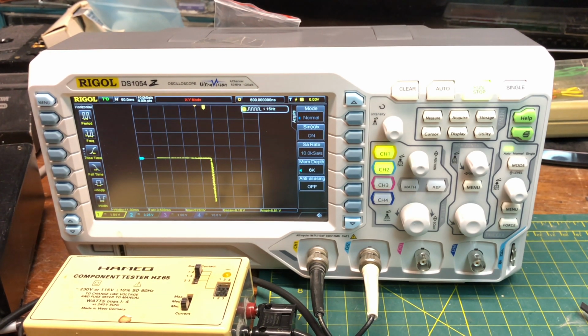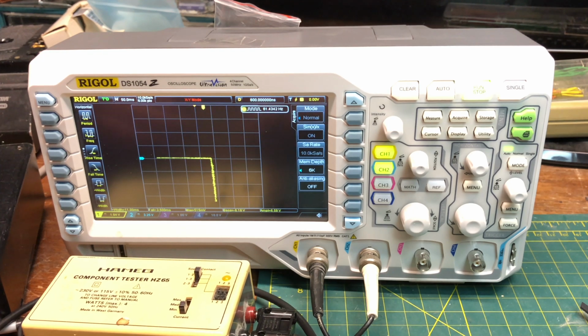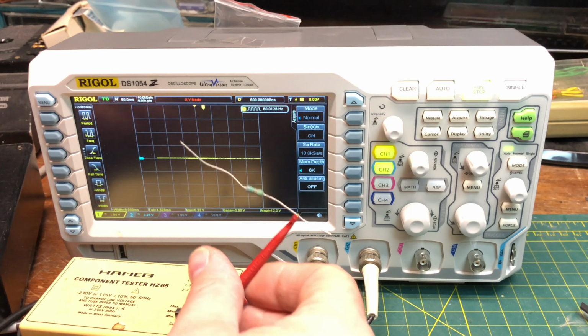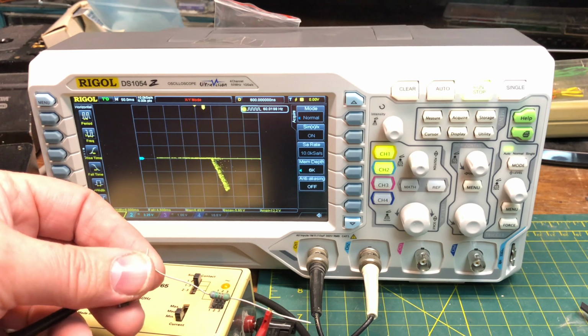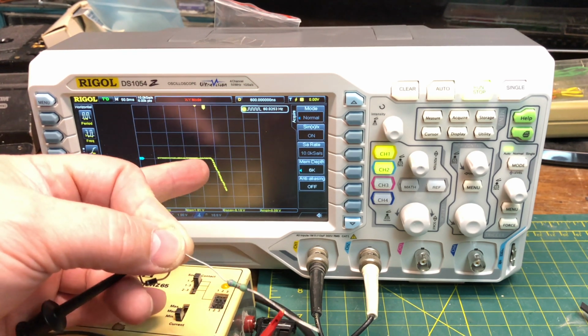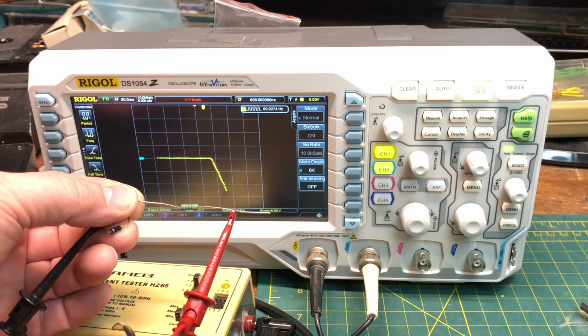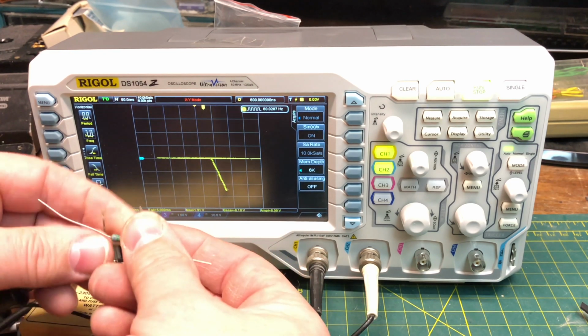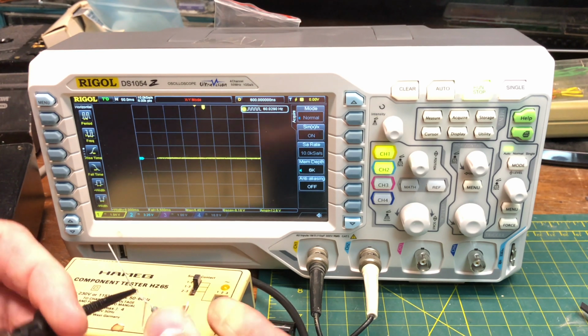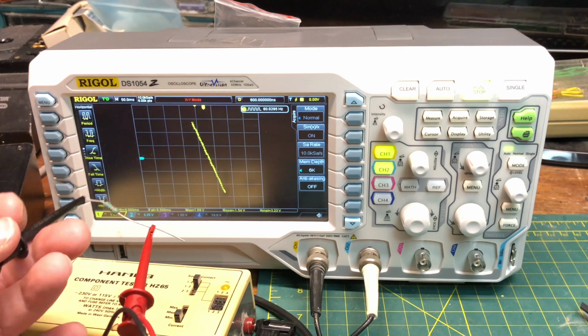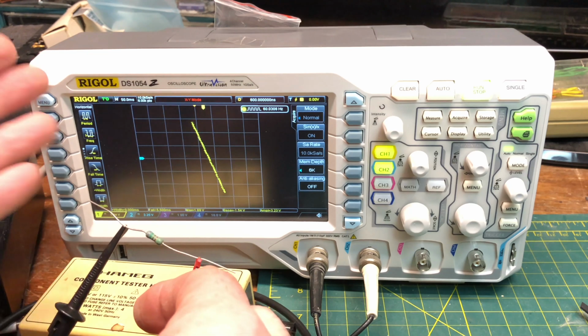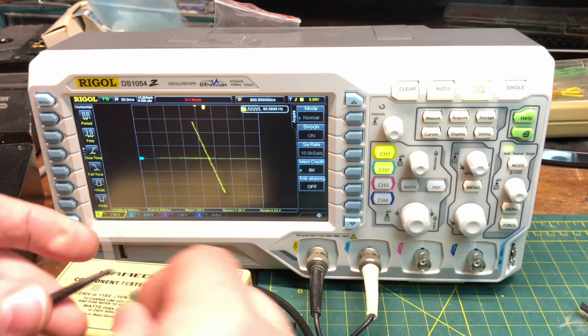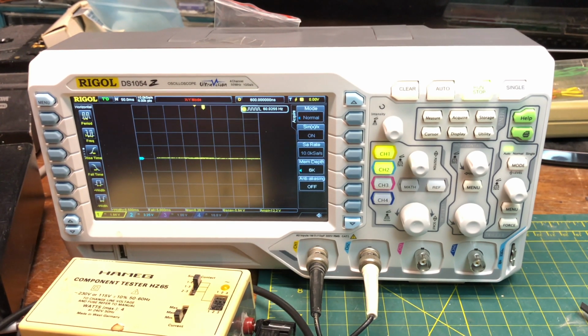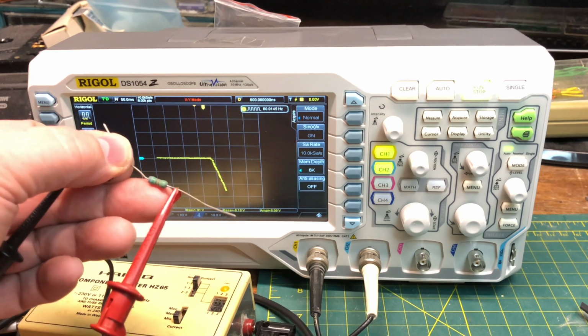And hold on a second. What if there was a resistor, a 750 ohm resistor, in line with that diode, what would happen? Well, that's what happens. So this slanted line is the resistance, the 750 ohms. I'll show you that by removing the diode. Okay, so there's our resistance value. 750 ohms is causing it to kind of angulate a little bit. So if you were testing in circuit and you had that pattern, then you'd know that you had a resistor tied in with your diode.